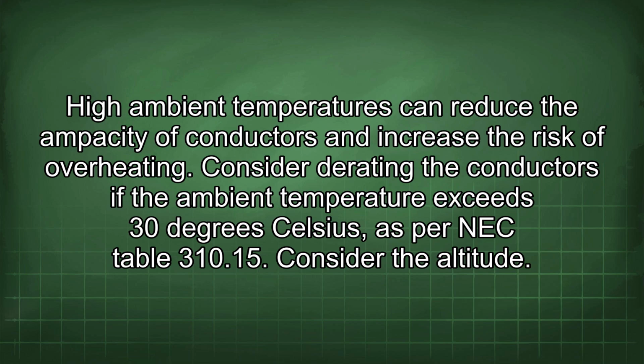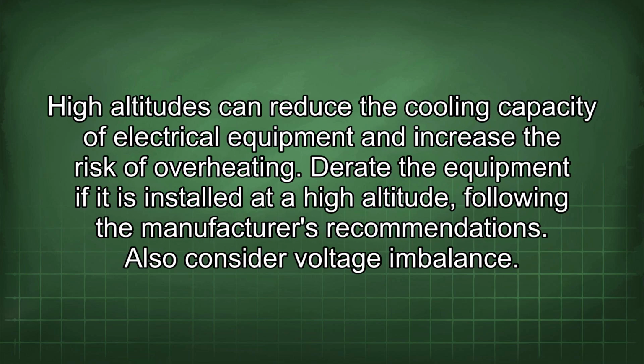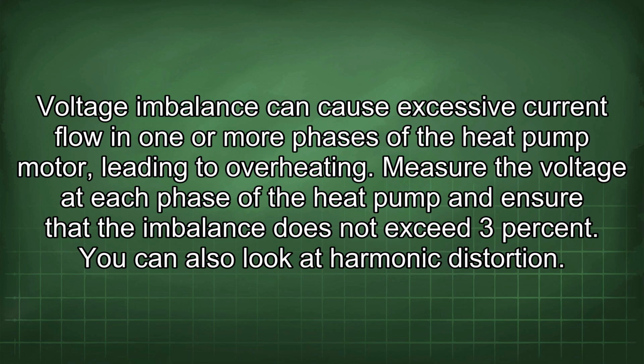Consider the altitude. High altitudes can reduce the cooling capacity of electrical equipment and increase the risk of overheating. Derate the equipment if it is installed at a high altitude following the manufacturer's recommendations. Also consider voltage imbalance. Voltage imbalance can cause excessive current flow in one or more phases of the heat pump motor, leading to overheating. Measure the voltage at each phase of the heat pump and ensure that the imbalance does not exceed 3%. You can also look at harmonic distortion.